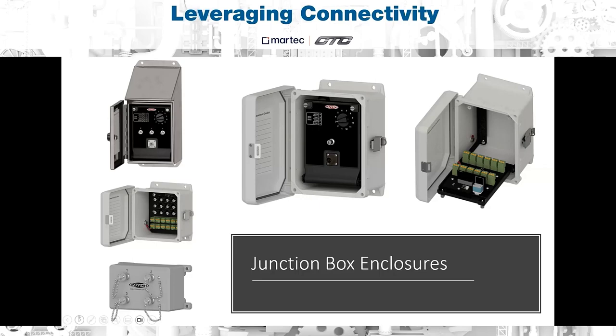One junction box that I would like to highlight is our iBox series. This can be seen in the top right 2 pictures of the slide. This junction box has a front panel that will conceal all of the terminal blocks and cables. However, it can also drop down for ease of cable installment. This is one of our more efficient solutions because it will only require you to connect your data collector to either the BNC or 2-pin mil connector once. And once you make that connection, you can take your reading from each sensor. All you have to do is switch the channel knob in the top right of the panel.